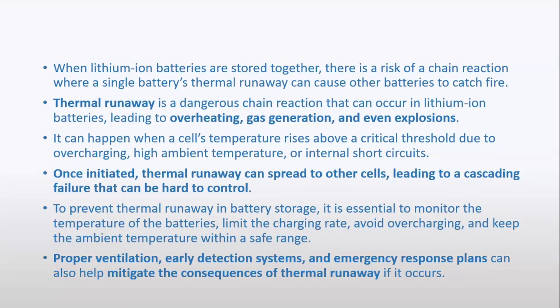The big threat with lithium batteries is what we call a thermal runaway, and I'm sure you've all heard this word, it's all over the news and the internet when you research batteries. This is a chain reaction that results even if one battery in a system, or one battery cell, is defective or gets punctured - you get overheating, gas generation, and even explosion in the batteries. This happens when the critical threshold of temperature is reached, which can be due to overcharging, even just high ambient temperature, or an internal short circuit in the battery itself.